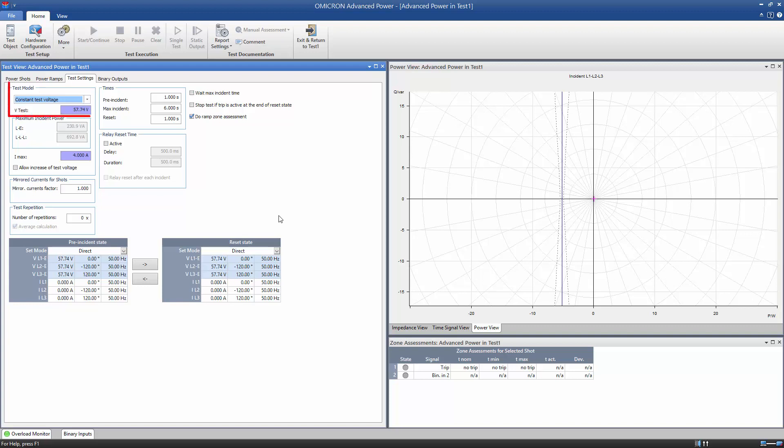We select either Constant Test Voltage or Constant Test Current as Test Model and specify its value as VTest or ITest. The respective other value is calculated by the test module and limited by the parameter IMAX or VMAX.